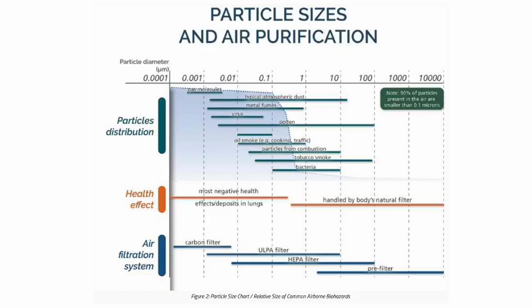Now, let's talk about the filtering system of your biosafety cabinet. The filters are the main part of the biosafety cabinet that do the protection, because the filters can provide decontamination of the air supplied and recirculated inside the biosafety cabinet. There are two types of standard filters used in biosafety cabinets: your HEPA filters, or high efficiency particulate air filters, and your ULPA, or ultra low penetration air filters.